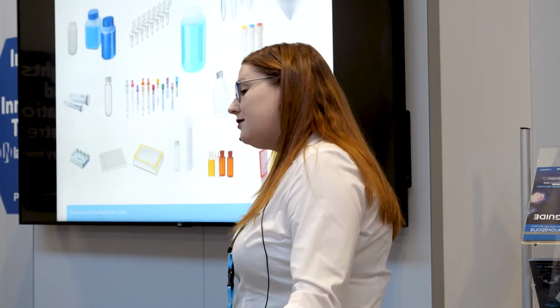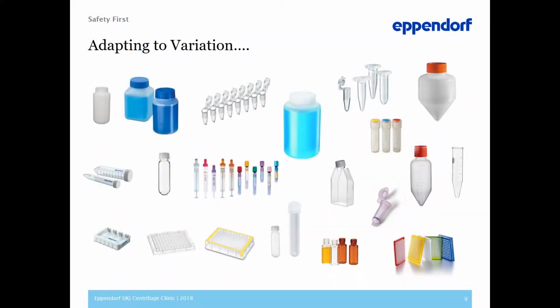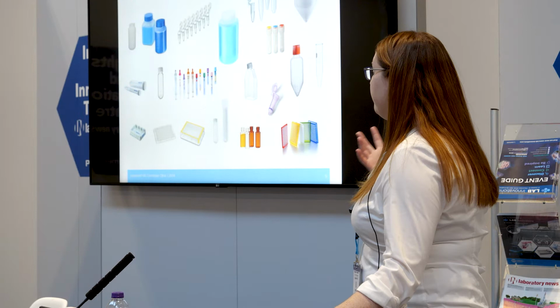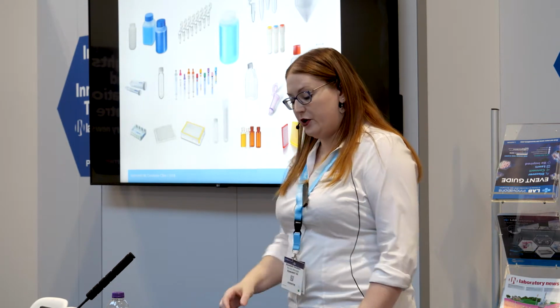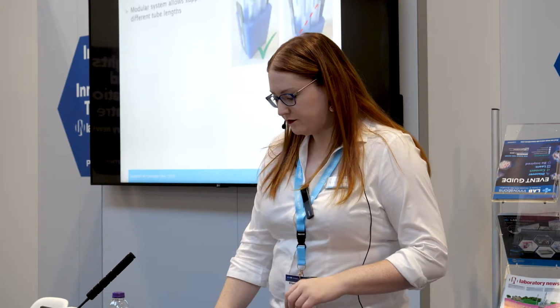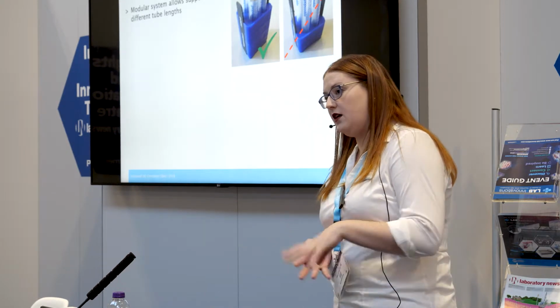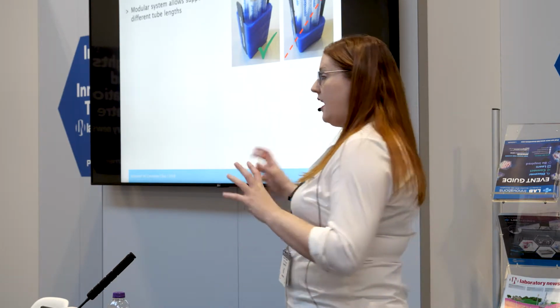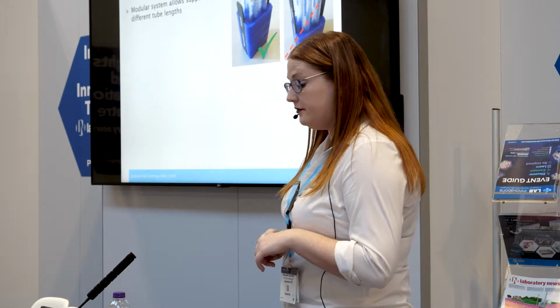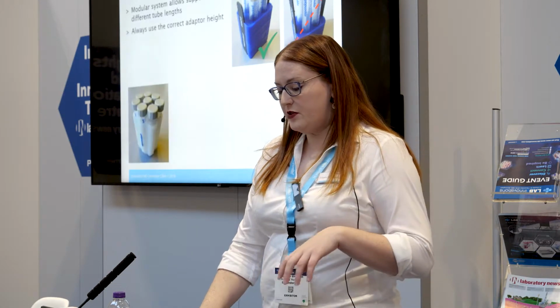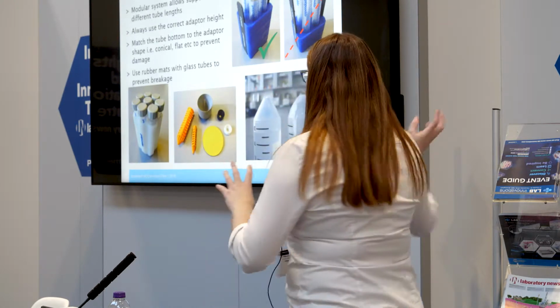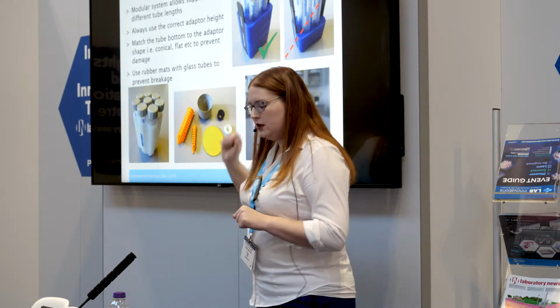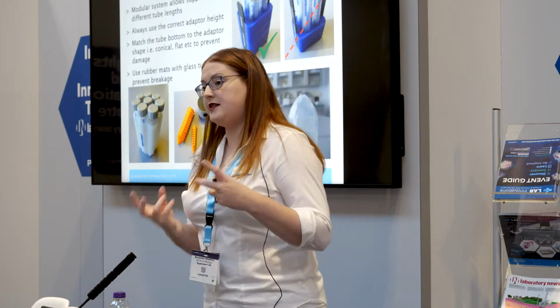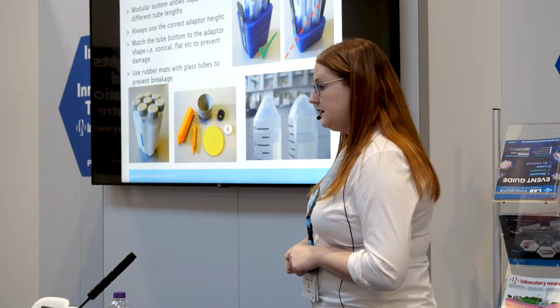But when it comes to swing out rotors in particular, one of the key things that manufacturers look at more and more is being able to adapt to variation and the vast number of different formats that scientists are increasingly working in. So, Eppendorf works with a modular system. Some of the other competitors do the same, but this is definitely what we have. This means you can support tubes of different lengths. Now, a key one for this is actually, this is quite a good example, 5ml tubes are the same shape as the bottom of a 15ml conical.